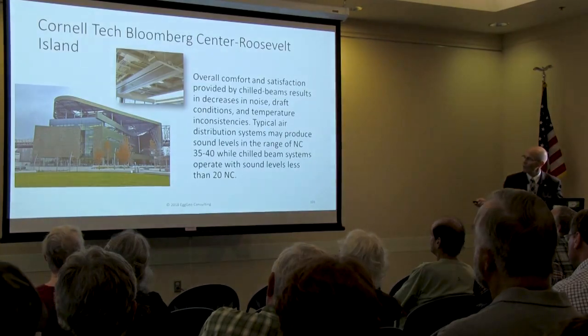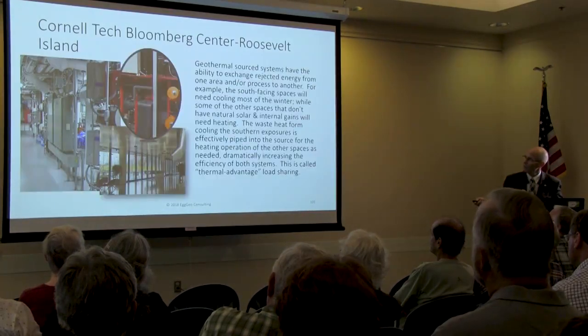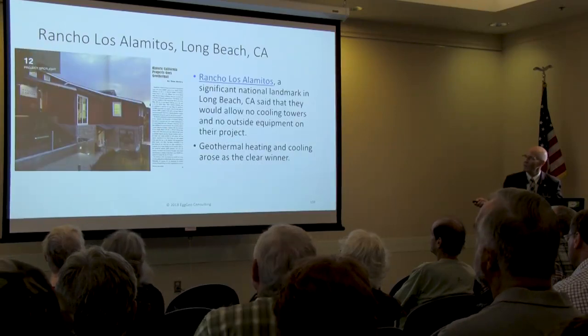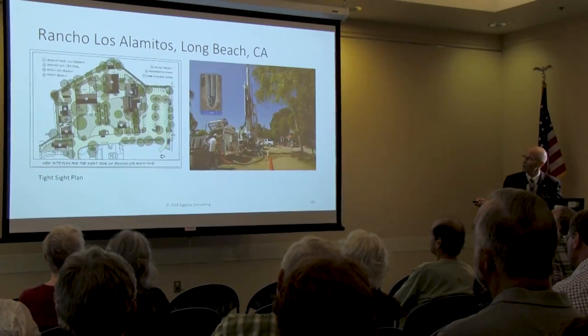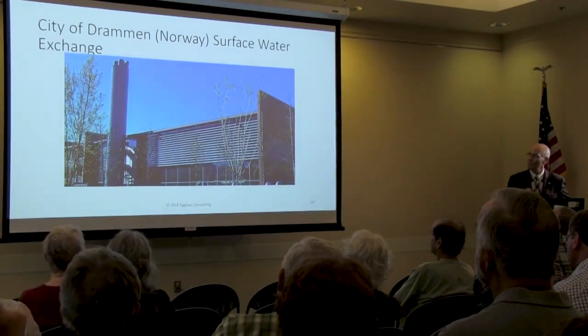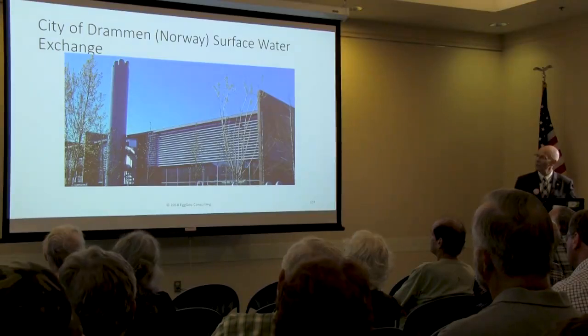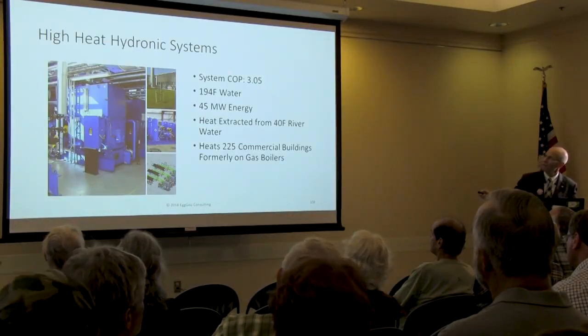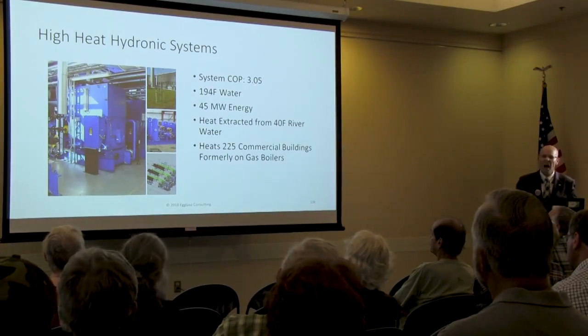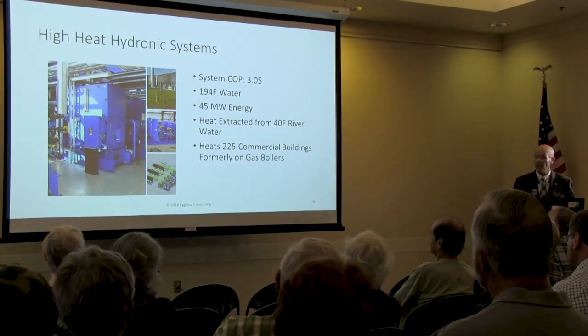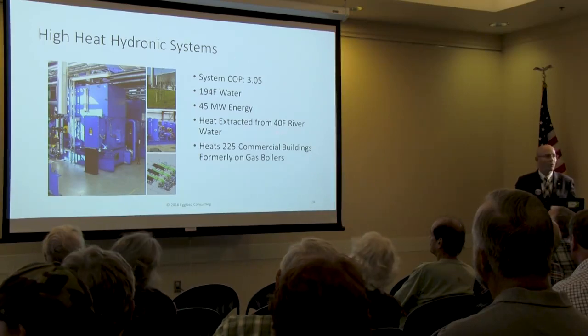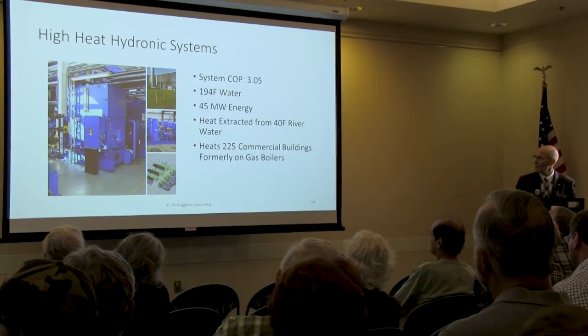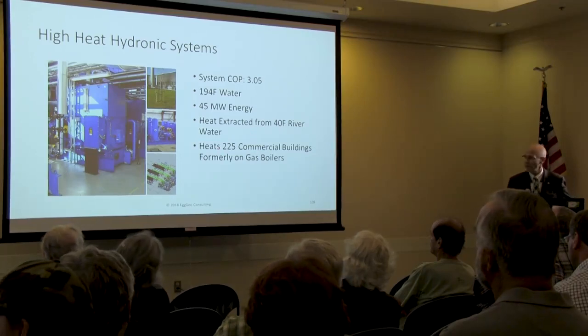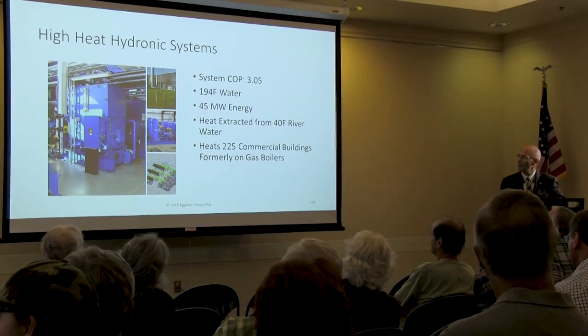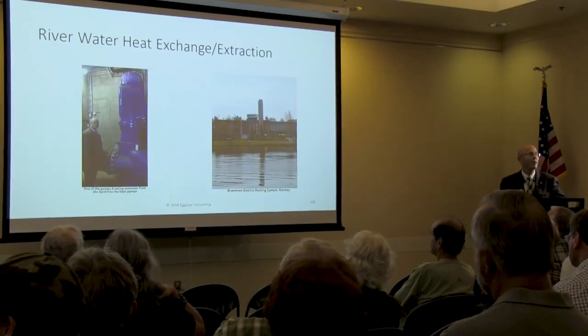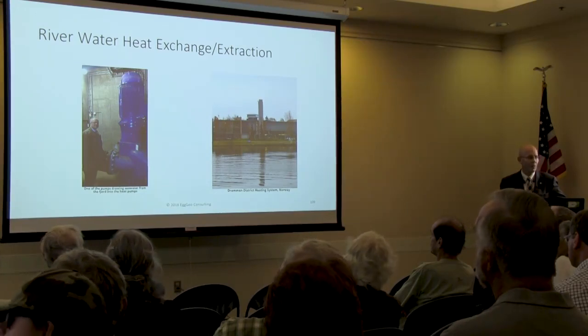We talked about Cornell campus and Rancho, so I just have a ton of case studies here. Rancho Los Alamitos and Long Beach. Here's the city of Drammen, Norway. This is the one I wanted to get to, because they were able to attain a system COP of 3.05, 194 degree water distributed throughout the entire city, heat extraction from 40 degree river water, heats 225 commercial buildings formerly on gas boilers. It's a fantastic project. The city of Stockholm, Sweden has been on a river water system for all of Stockholm since the 80s.